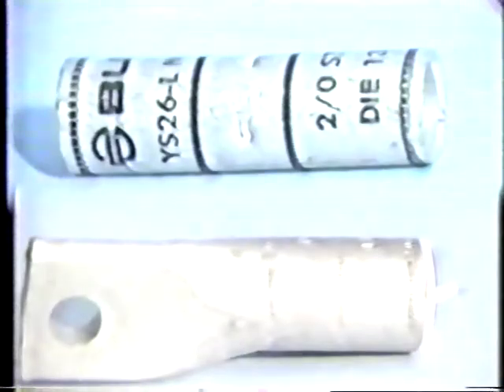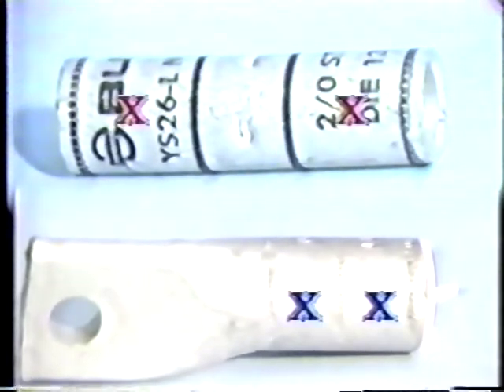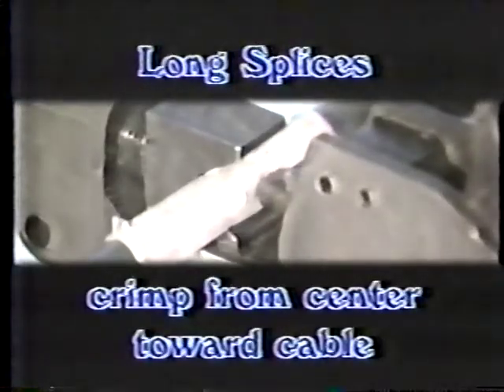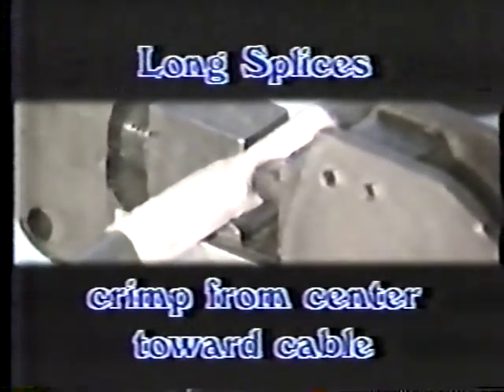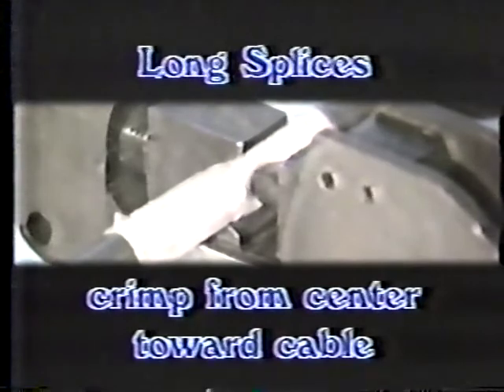Longer terminals may require more than one crimp. The color-coded bands on the terminal indicate the number and location of the crimps required for a proper installation. If a splice or aluminum terminal is being installed, the crimp should be placed between the color-coded rings or knurlings. Longer splices requiring more than one crimp should be crimped from the center of the connector towards the cable.